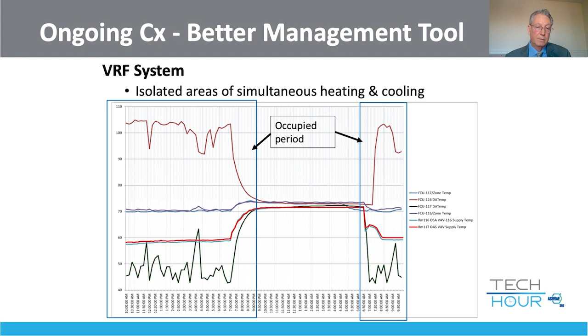In open floor plans, you can have crossover of controls where you see this kind of fighting, where one is in heating and one is in cooling, because you haven't calibrated the sensors for both zones to be accurate, or you haven't changed the control operation to be able to use an averaging of the two so they're not fighting each other.